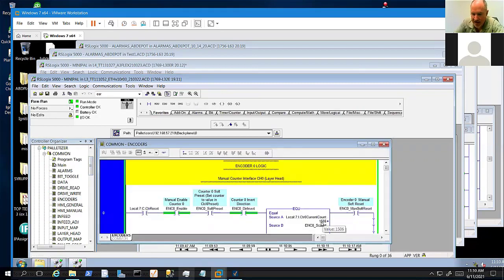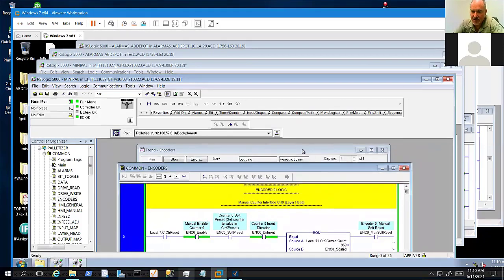Right, if I look at the raw count, you can see this one's 1500. Neither of these encoders should ever leave the range 0 to 1800. You can see this one just moved here. So if I look at the trend, you'll see that the encoder moved.